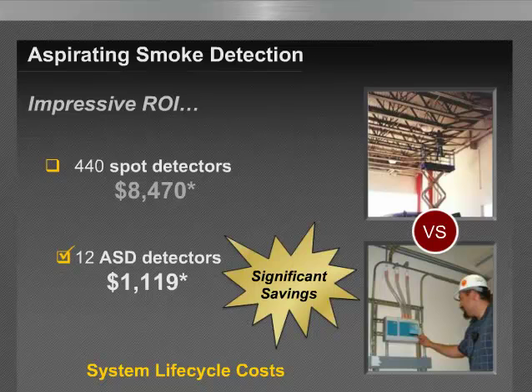And we take the same comparison with 12 aspirating smoke detection detectors to serve the same space. And again, the test and inspection only occurs at the very last sample port of each pipe run. And with that, you have a comparison at $1,119, about an 86% savings. So that presents itself as a significant return on investment for these types of technologies.